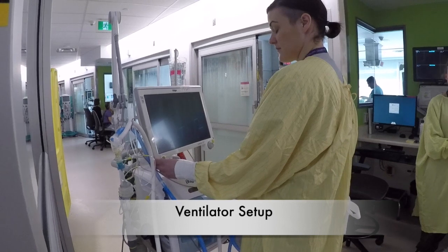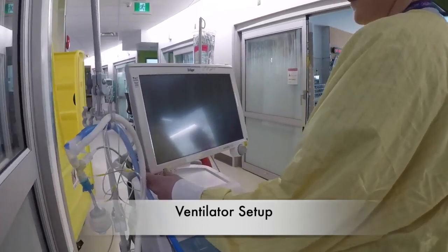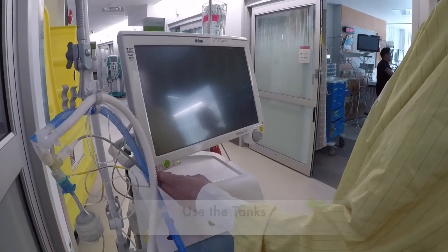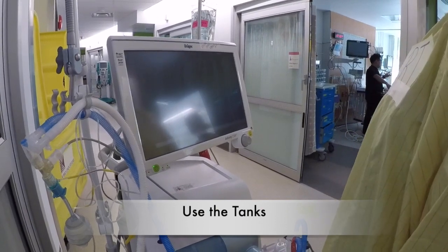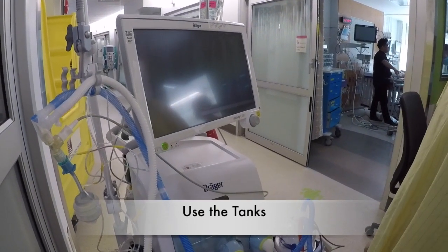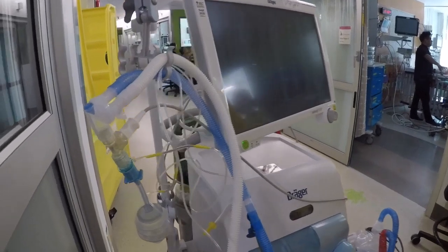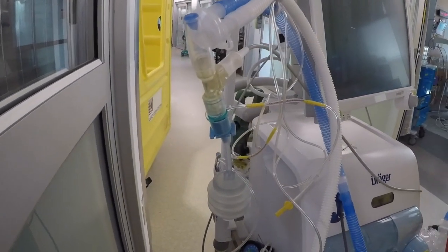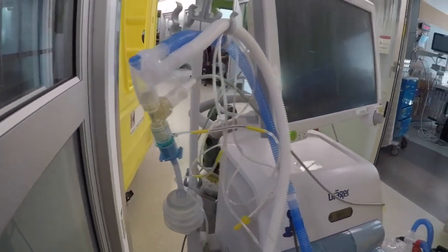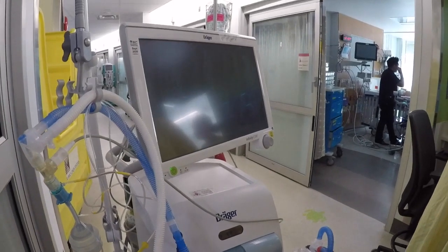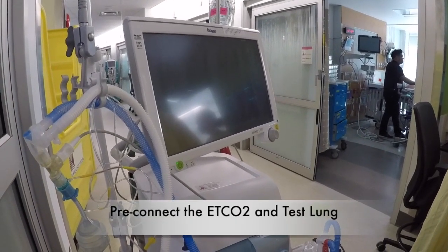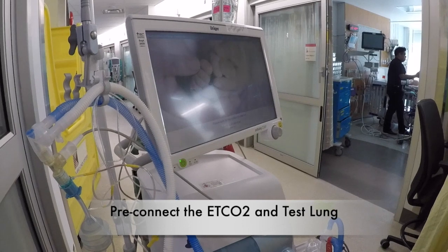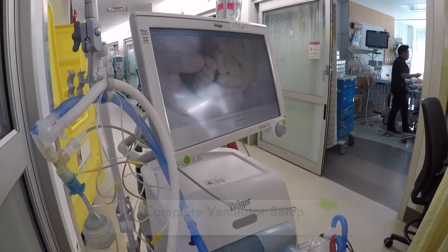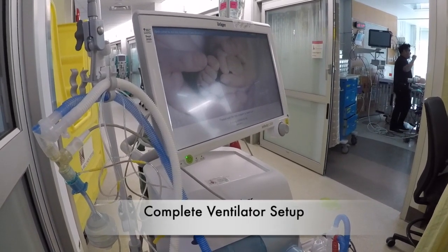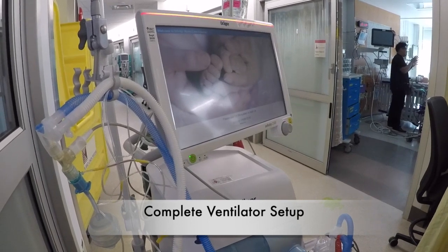All of the ventilator setup can be done outside of the room as well. Set up the ventilator on the tanks. Doing this will allow more flexibility in where the ventilator can be placed during the procedure. It will also allow the respiratory therapist to connect the ventilator to the wall gas outlets after the intubation to decrease the workload prior. Connect the circuit to the end-tidal CO2 and a test lung. The ventilator settings can then be entered such that the ventilator can be started prior to the intubation.